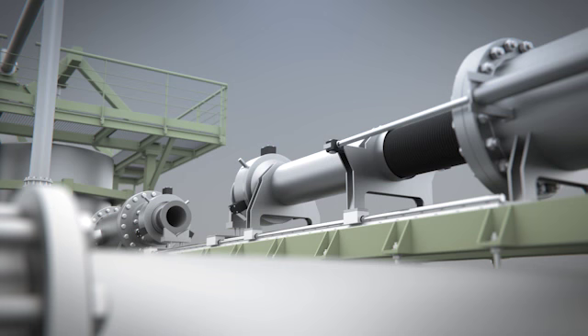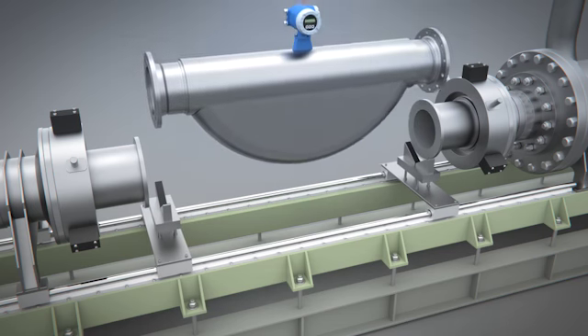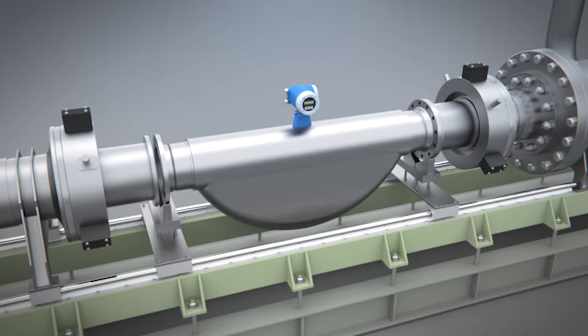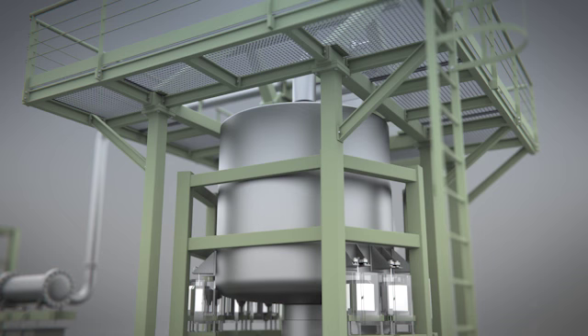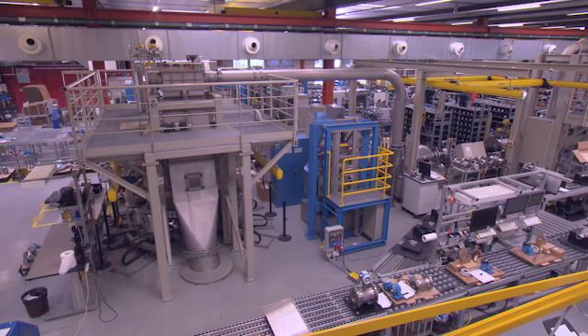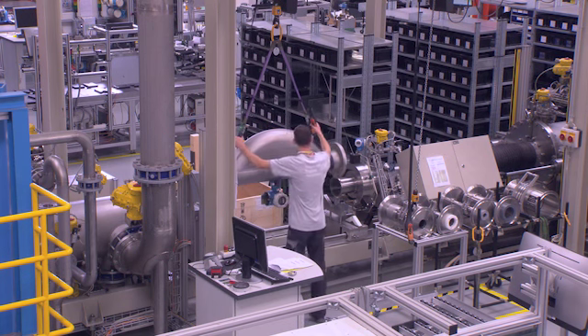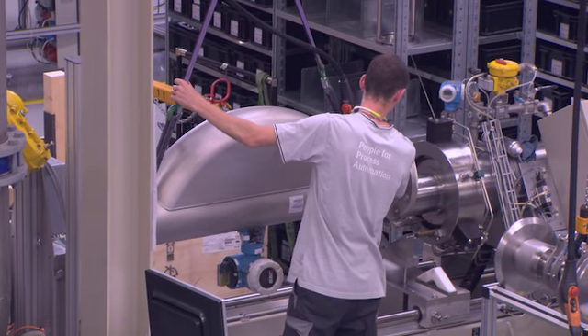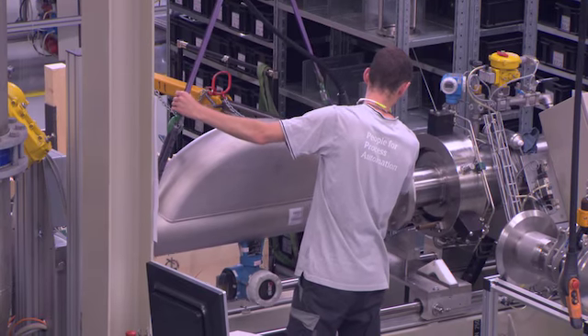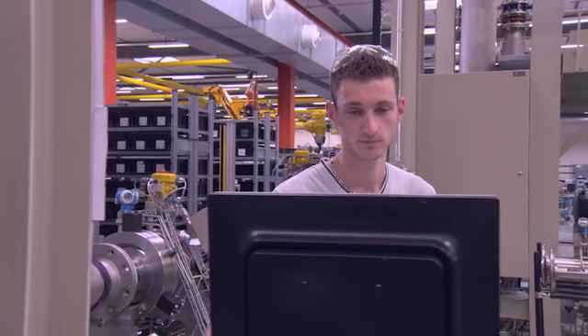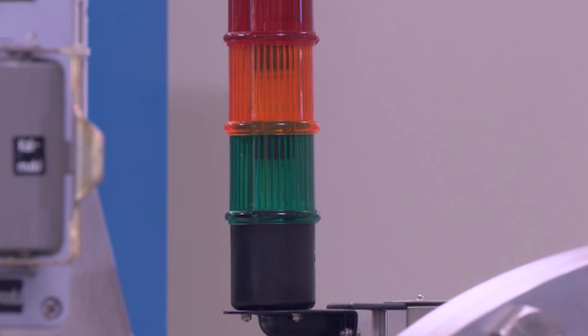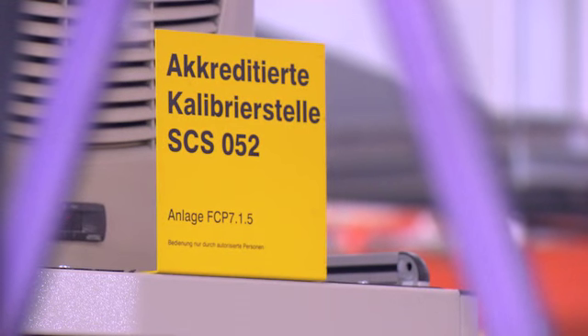As the leader in calibration metrology, Endress and Hauser defines the highest standards of quality and precision. Every calibration system we build is designed and operated according to stringent, internationally recognized criteria. No other flow meter manufacturer maintains as many calibration facilities worldwide as Endress and Hauser. But how can we, as a global company, prove that our calibration rigs reproduce the flow variable correctly and thus meet the high standards that are required of a reference?